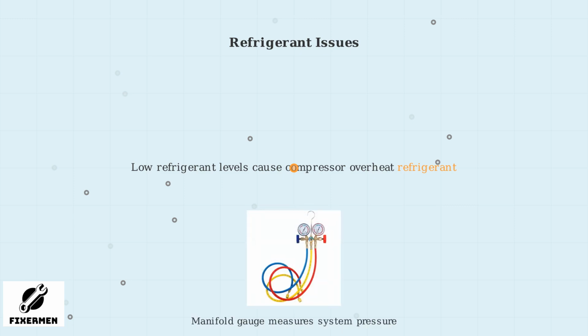If basic checks like cleaning coils and ensuring proper airflow don't resolve the E4 error, the problem likely involves the refrigerant system or electrical components. Let's examine refrigerant issues first. Low refrigerant disrupts the cooling cycle, causing the compressor to work harder and overheat. This imbalance can be detected through pressure testing, which requires professional tools and certification.